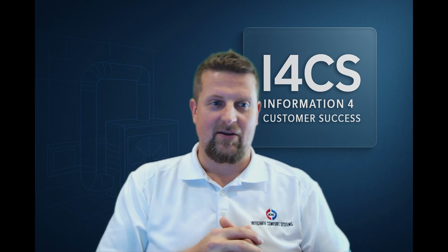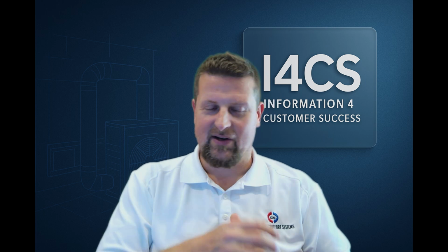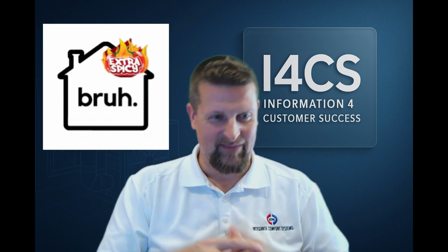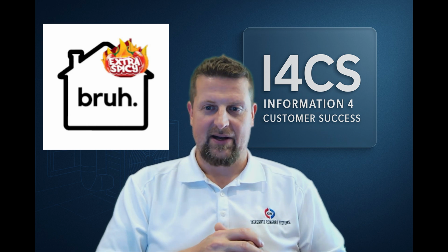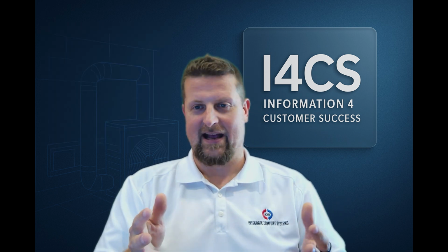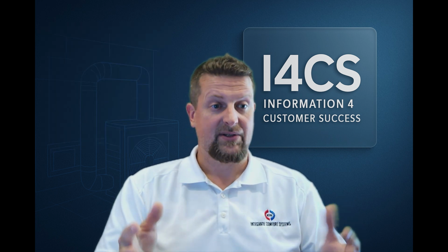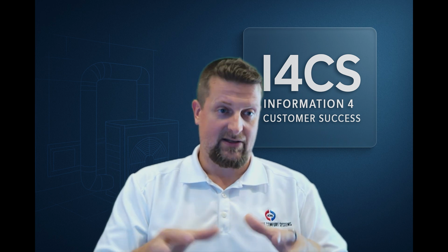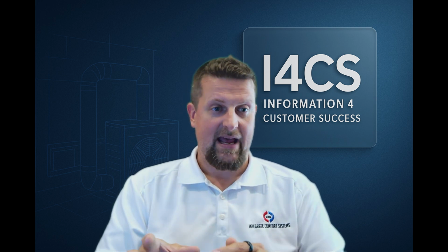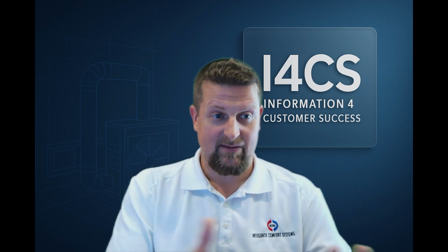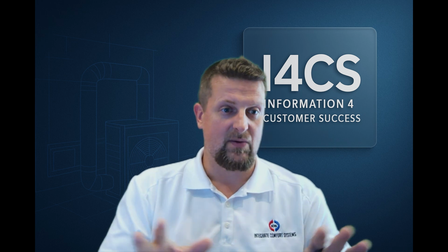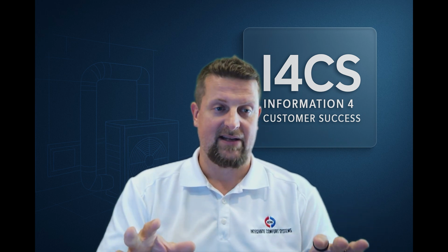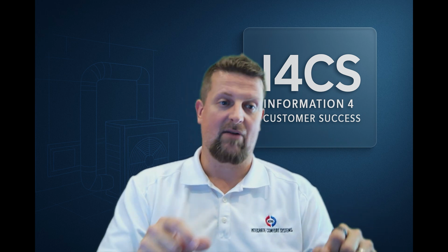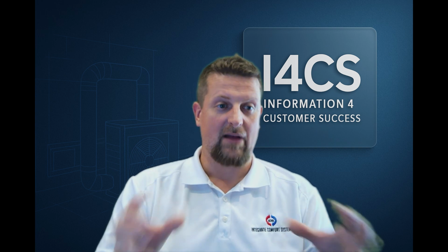So, why don't you give me an air conditioner that, just when it hits 100, I'm going to be happy? Give me some extra BTUs. That really is not the proper way to do it. Has that been done? Absolutely. And has that not caused problems? Yes, absolutely. However, you are asking for a scenario of causing problems. And again, for the other 99% of the year, you are not doing yourself justice. You are not running the best efficient system for the house. You are not removing humidity as well as you should.